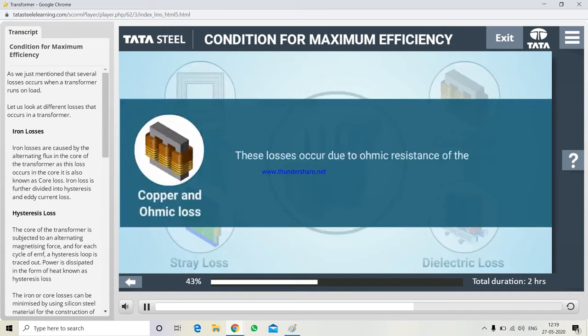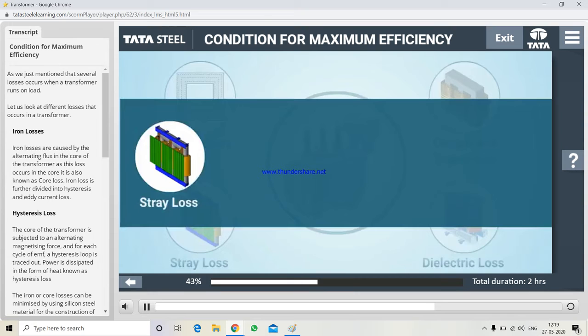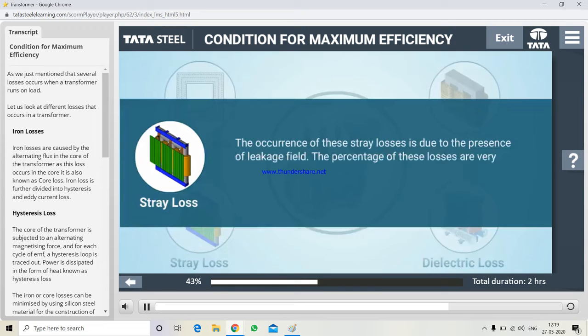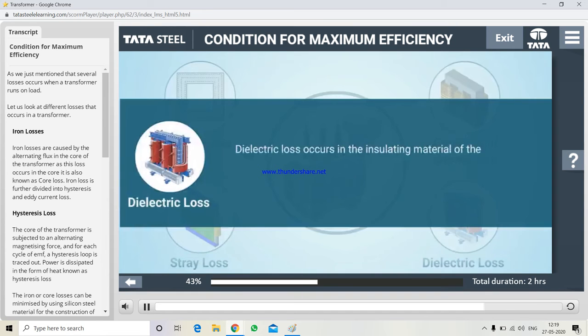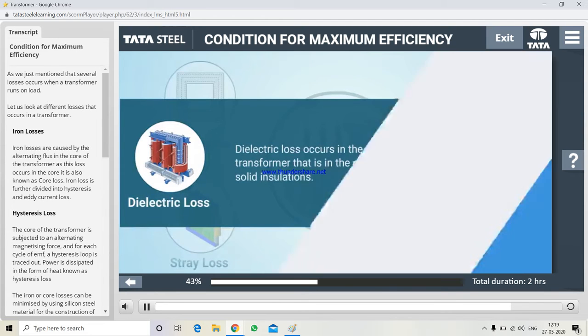Copper and ohmic loss. These losses occur due to the ohmic resistance of the transformer windings. Stray loss. The occurrence of these stray losses is due to the presence of leakage field. The percentage of these losses is very small compared to the iron and copper losses, so they can be neglected. Dielectric loss. Dielectric loss occurs in the insulating material of the transformer, that is, in the oil of the transformer or in the solid insulations.